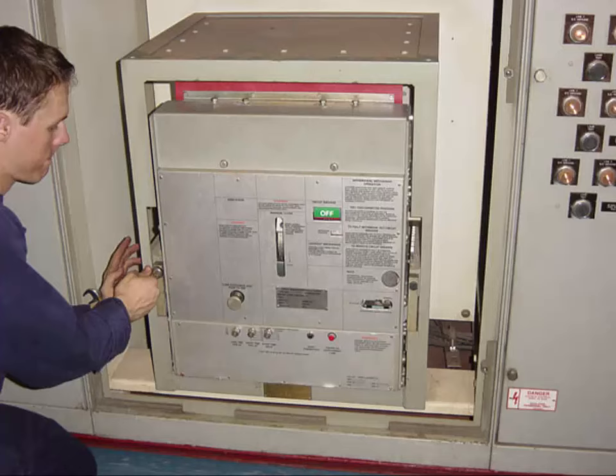One of them is instantaneous. If there was a very high current flow, these are set so that they would open instantaneously or very, very quickly to protect the circuit. Now, if it's a minor overload, they'll have a time delay before they open. This could be because we are an unmanned ship. This could be that a piece of equipment's been put on the line, and this limited amount of overload would allow a generator to come on the line, synchronize, and put itself on before it tripped.